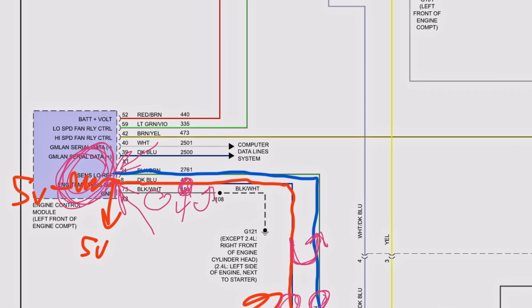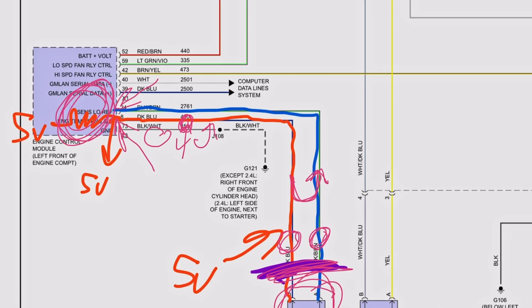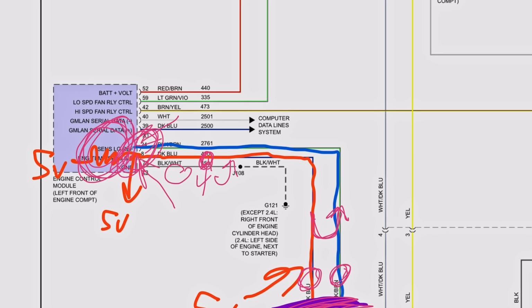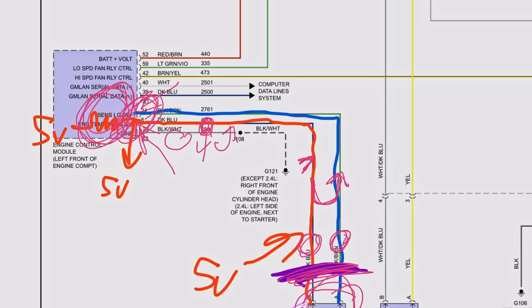Make sure you're checking your voltages at your sensor and at your computer. Then if you think there's a problem in the wire, like maybe it's rubbed a little on a sharp corner, you could unplug the wire at the computer, unplug it at the temp sensor, and then load test them. So what do I mean by load test them?